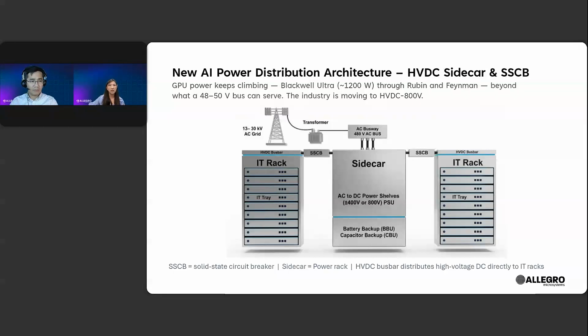So in the new 800 volt architecture, we started to see the IT rack and the power rack being separated, like the photo we show on the slide. The IT rack mainly focuses on computing, like CPU and GPU. Between the IT rack and power rack, there is an 800-volt DC link, and this creates a new protection point before the high voltage DC enters the IT rack, for rapid protection. We call it SSCB, solid state circuit breaker. In the power rack, we call it the Sidecar, which handles power conversion. Its output supports 800-volt DC power distribution. With higher voltage, we can make the power architecture easier to scale.